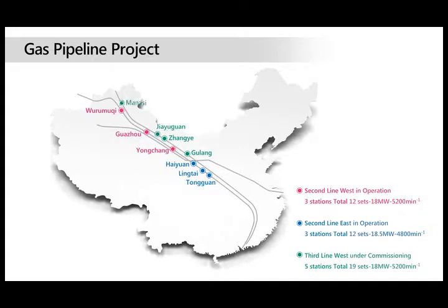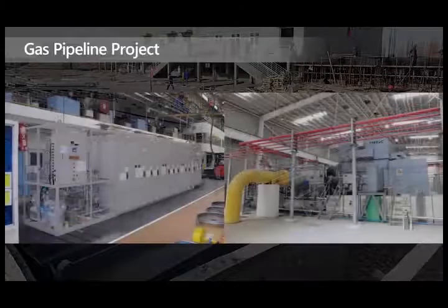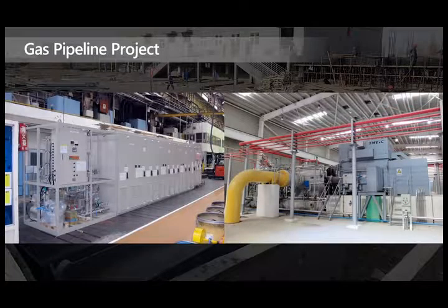One example is the West-East Gas Pipeline project in China, where TMEIC has supplied high-speed synchronous motors, 31 sets of 18 megawatt, 5,200 rotations per minute, and 12 sets of 18.5 megawatt, 4,800 rotations per minute. Now we can see an apparent technical trend of compressor drivers from gas turbines to LCI, or load commutated inverter, and from LCI to VSI, or voltage source inverter.